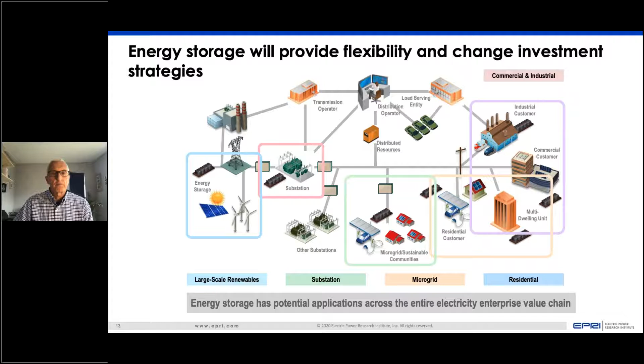The other thing happening with electric vehicle chargers that I think is very important, as we look at applying more fast chargers and extremely fast chargers with very high megawatt level power ratings, is that those will often be installed with energy storage so we can minimize the impact on the grid and the capacity requirements. So if we have a fast charger integrated with energy storage, we have to look at all the potential for that combination to provide flexibility services to the grid as well as electric vehicle charging potential. Very exciting time for energy storage in general, and especially how it relates to electric vehicle charging.